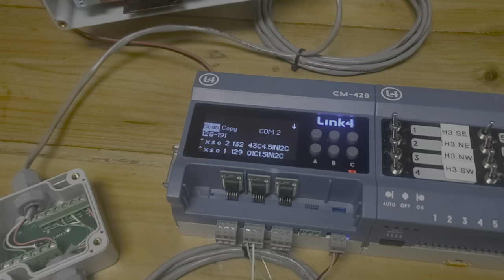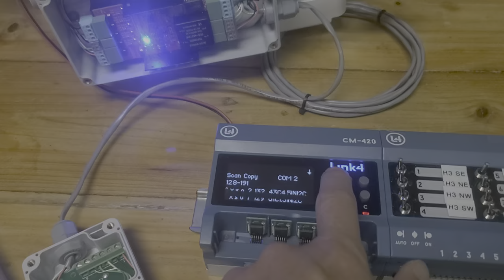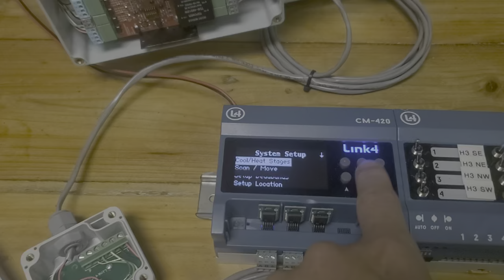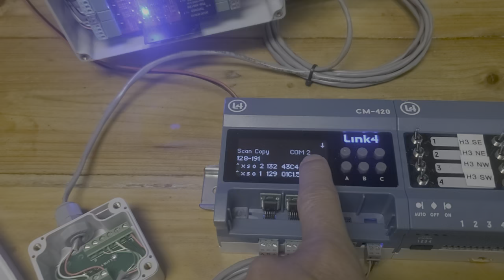Another common troubleshooting method is, let's say you can't find it - is the problem the cable, this module, or this controller? One common way to troubleshoot is to unplug this and move it to COM1. Again it's Modbus, so move this to COM1, and instead of scanning COM2, scan COM1 instead.